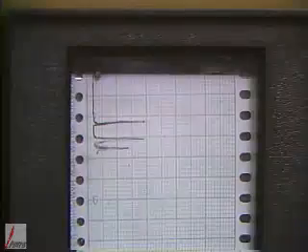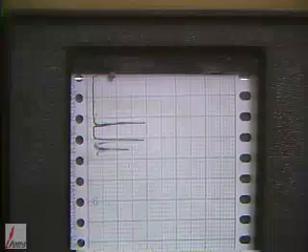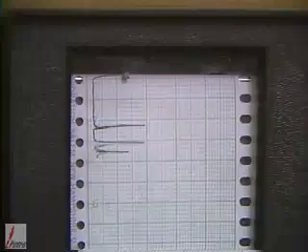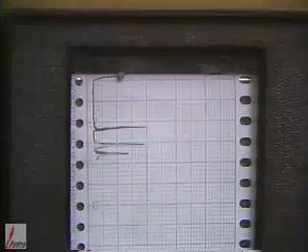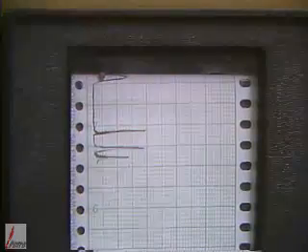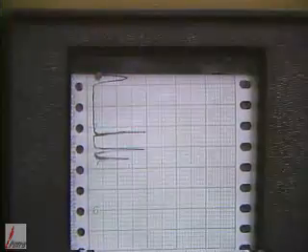Another portion of the mud gas sample is passed into a continuous flow loop. A batch sample is taken every few minutes for identification of individual gas components, which makes up the total gas reading. This hydrocarbon compound analyzer uses gas chromatographic analysis, which typically takes 3 or 4 minutes to separate the compound types and measure their concentrations. Therefore, its output is cyclic rather than continuous.